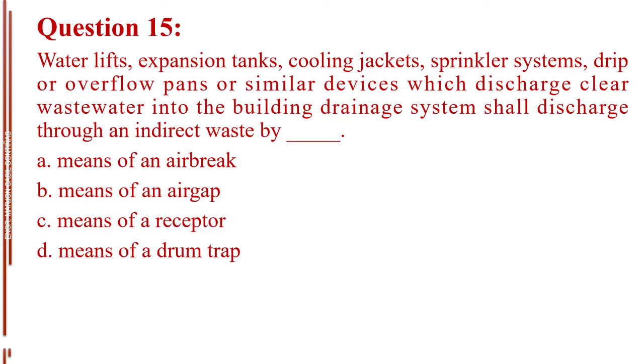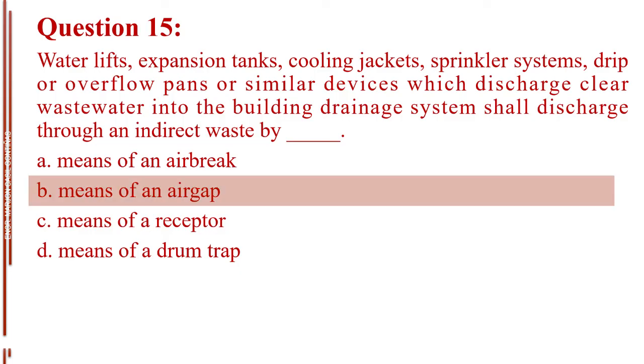Question number 15. Water lifts, expansion tanks, cooling jackets, sprinkler systems, drip or overflow pans or similar devices which discharge clear wastewater into the building drainage system shall discharge through an indirect waste by blank. Letter A, means of an air break. Letter B, means of an air gap. Letter C, means of a receptor. Letter D, means of a drum trap. The answer is Letter B, means of an air gap.